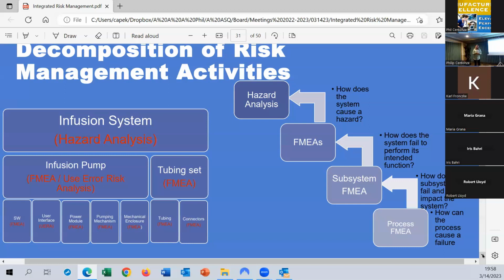So essentially, it's like your Windows File Explorer, right? You click on the plus, and you get all the files in there. Well, this is like saying, okay, here I identify all my faults at the system level, and then here I can be more specific and tell you, infusion pump, these failures will lead to this one hazard here. Right? And I can continue to drill down, and depending on the criticality of the system or the components, I could drill down as low as possible. Obviously, the more FMEAs that you do and the more you reduce failure modes, the better performance of your system, right, from a reliability standpoint.